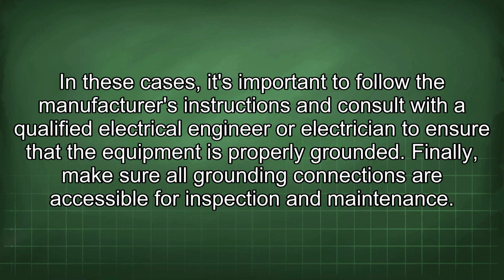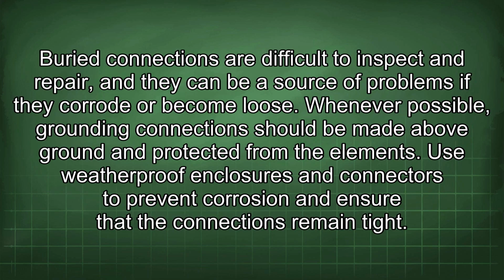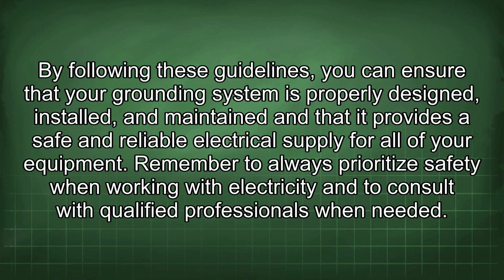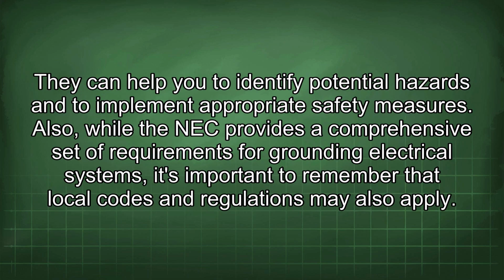Finally, make sure all grounding connections are accessible for inspection and maintenance. Buried connections are difficult to inspect and repair, and they can be a source of problems if they corrode or become loose. Whenever possible, grounding connections should be made above ground and protected from the elements. Use weatherproof enclosures and connectors to prevent corrosion and ensure that the connections remain tight. By following these guidelines, you can ensure that your grounding system is properly designed, installed, and maintained, and that it provides a safe and reliable electrical supply for all of your equipment. Remember to always prioritize safety when working with electricity and to consult with qualified professionals when needed. They can help you to identify potential hazards and to implement appropriate safety measures.